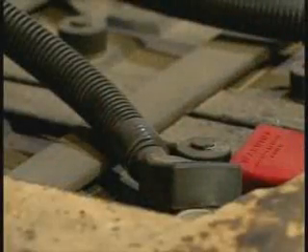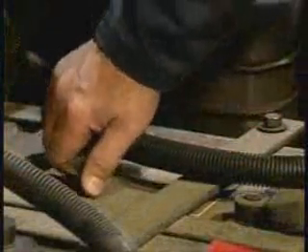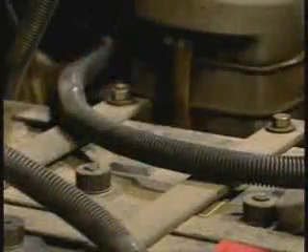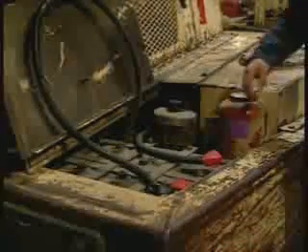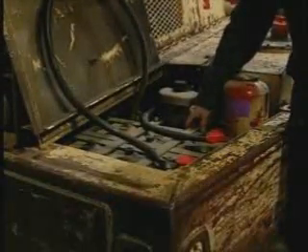Additionally, the battery cables need adequate mechanical protection. The fill caps must be in place and secured to prevent electrolytes from splashing out of the battery. The battery box must be of sturdy construction, and all batteries must be secured to prevent movement and must be protected from external damage by position.